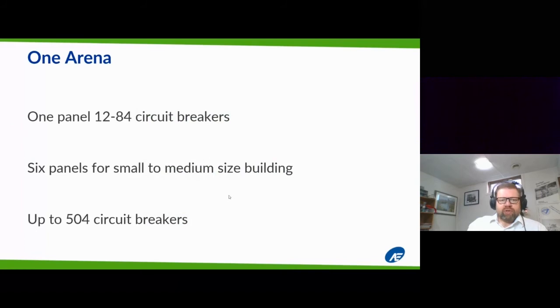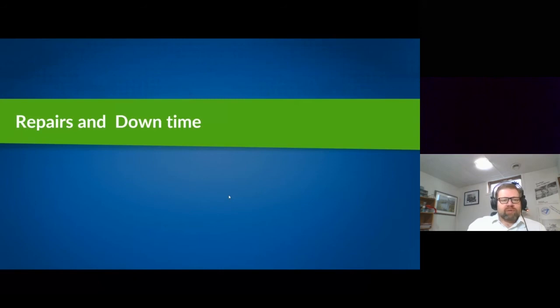So if you look at one arena, you might have 6 panels across it. Each panel could have between 12 and 84 circuits, so you're looking at about 500 circuit breakers. And later I'm going to tell you that about 1 in 20 of those circuit breakers aren't going to work after 30 years. So that means you're going to have 25 circuit breakers in this arena that is 30, 40 years old that aren't going to work when you need them to. So if they're not going to work, now you have to look at repairs and downtime. So you've got your availability, you've got your reliability.